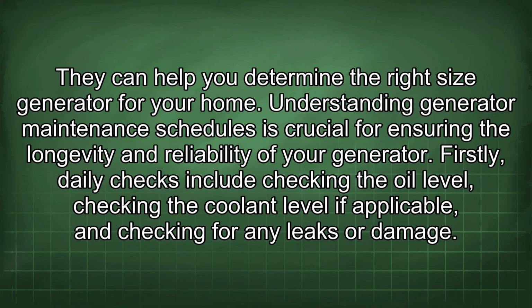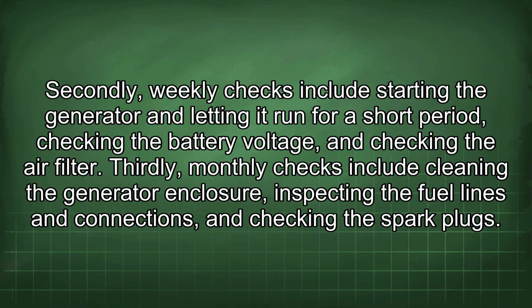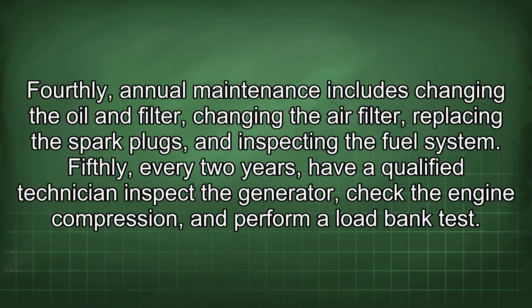Understanding generator maintenance schedules is crucial for ensuring the longevity and reliability of your generator. Firstly, daily checks include checking the oil level, checking the coolant level if applicable, and checking for any leaks or damage. Secondly, weekly checks include starting the generator and letting it run for a short period, checking the battery voltage, and checking the air filter. Thirdly, monthly checks include cleaning the generator enclosure, inspecting the fuel lines and connections, and checking the spark plugs.